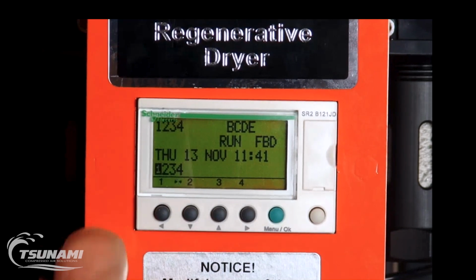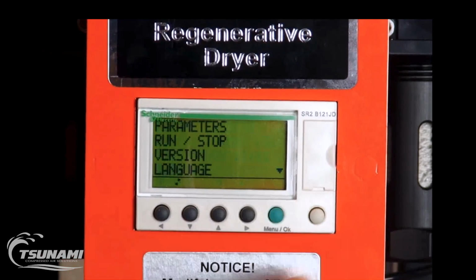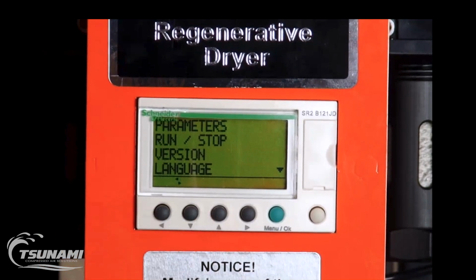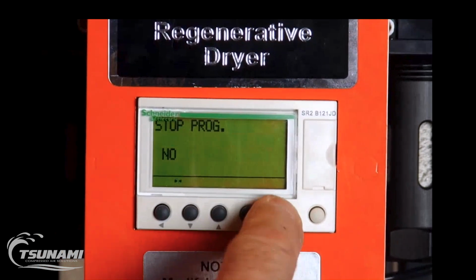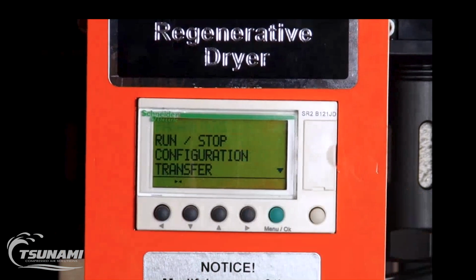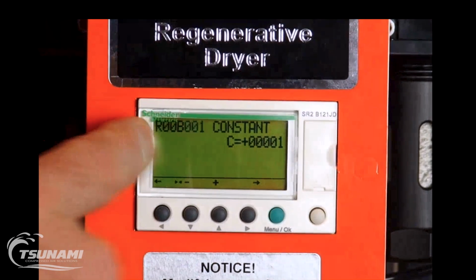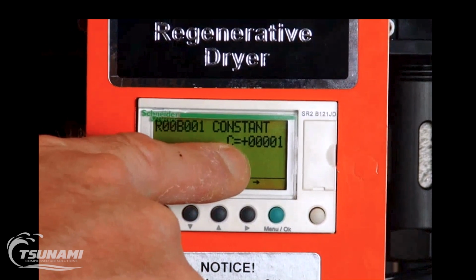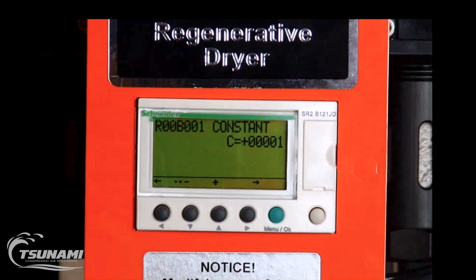If we want to change that, again, we want to get into run stop our program. Yes, we do want to stop it. We want to get back to our parameters. Block 1C is now at a constant value of plus 0001. We now want to change that to 5 because when it receives an input, we want it to immediately pause the drying cycle. And then when that signal is removed, it will immediately pick up where it left off.